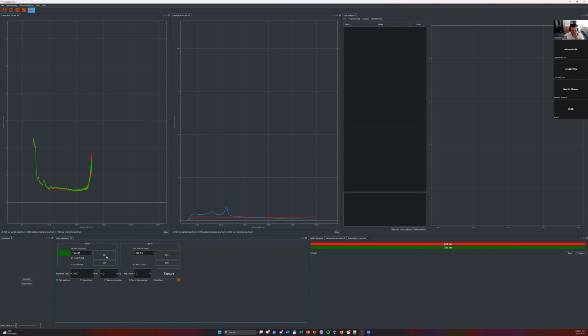Well, it's not necessary for identification. For identification, we only have the fingerprint region. But I can just show you that we can perform background correction for the other channel as well. Oh, sorry, I clicked reset. Now we have to capture again. Capture for the 660 channel. And back to 785, we capture and we click enable. And as you can see, the signal is at the 0 level now.